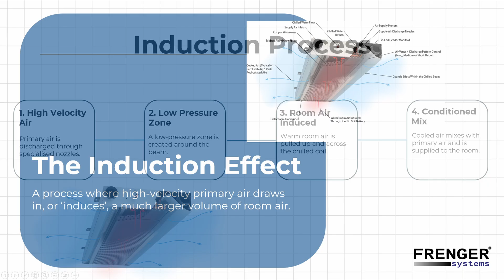Let's walk through it. First, that primary air we talked about gets squeezed through these tiny specialized nozzles, making it shoot out at a really high speed. This fast jet of air creates a low-pressure zone right around it. And, physics being physics, the higher pressure air in the room, which is the warm air, is naturally drawn towards that low-pressure spot. So the room air gets actively sucked up into the beam and over the chilled water coil. Finally, that newly cooled room air mixes with the fresh primary air, and the blend is gently distributed back into the space. The result of this whole induction process is a massive multiplication effect.